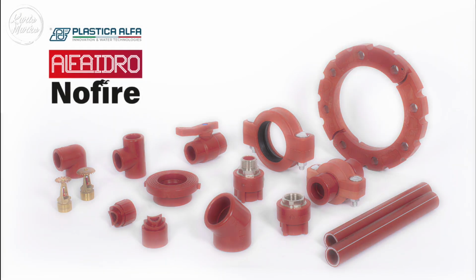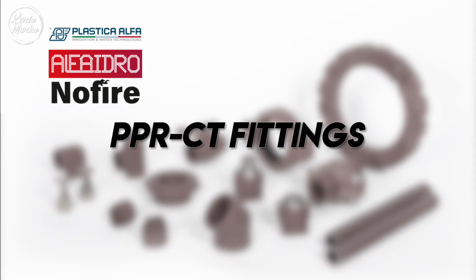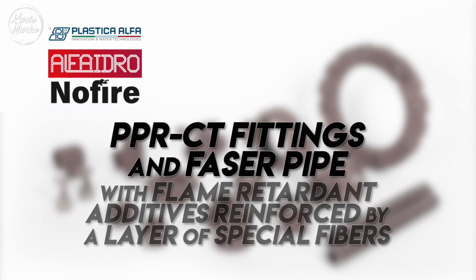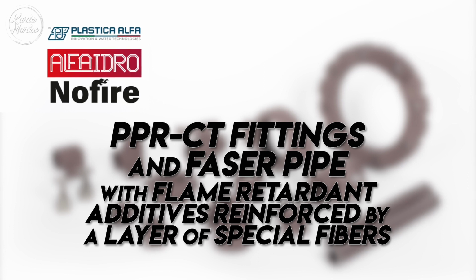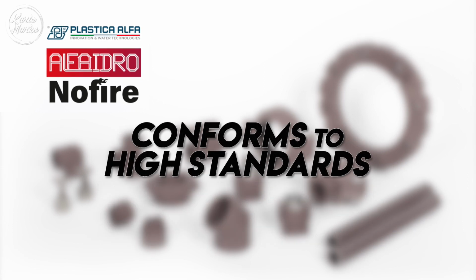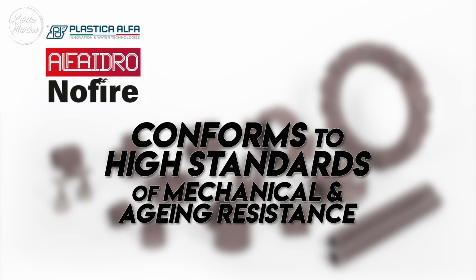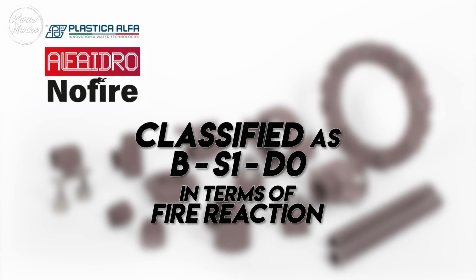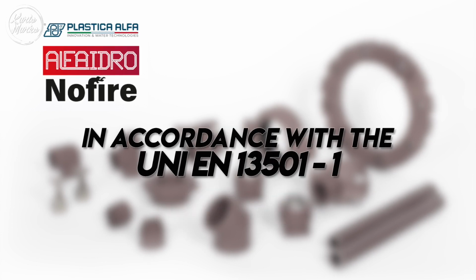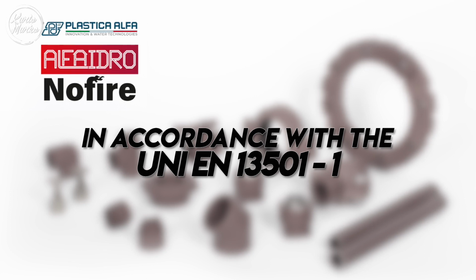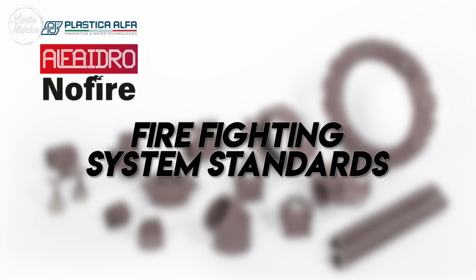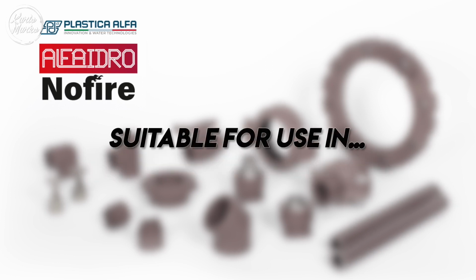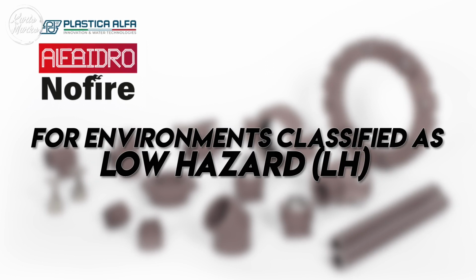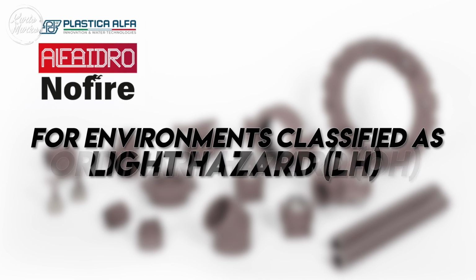The Alfaidro No Fire system is composed of PP-RCT fittings and a faser pipe containing a flame retardant additive reinforced by a layer of special fibers. It conforms to high standards of mechanical and aging resistance, and it has been classified as BS1D0 in terms of fire reaction. This is of course in accordance with the UNI EN13501-1 or the firefighting system standards. This makes it suitable for use in environments classified as low hazard or ordinary hazard, and also for light hazards.